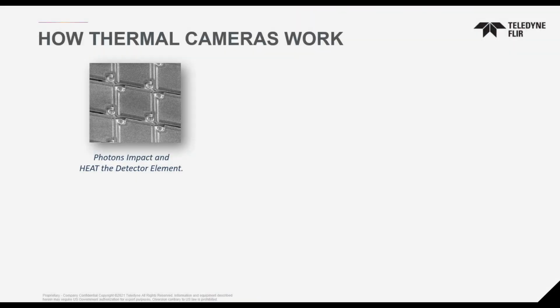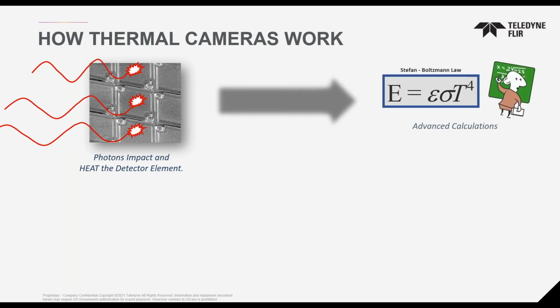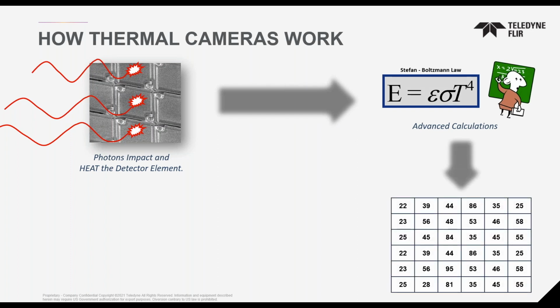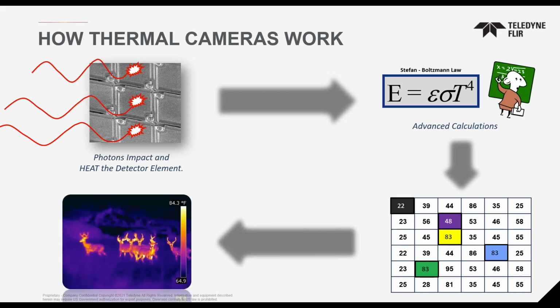So how they work: the photons impact and heat the detector element. Those photons are attacking, if you will, and we're capturing that information. We use the Stefan Boltzmann law to perform advanced calculations that let us associate specific pixel temperature measurements within the camera. We capture those values and associate colors to those data points to ultimately produce your thermal image.